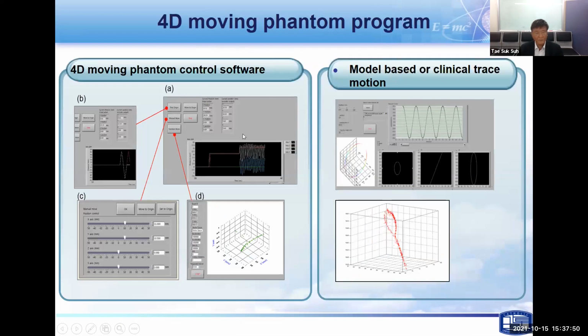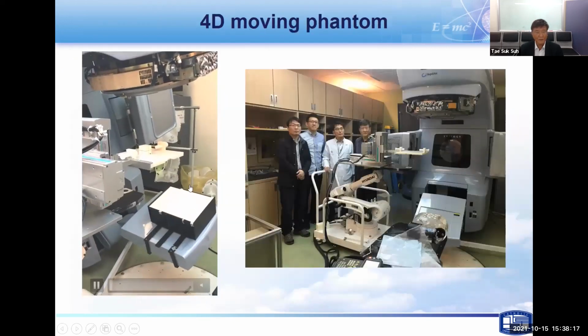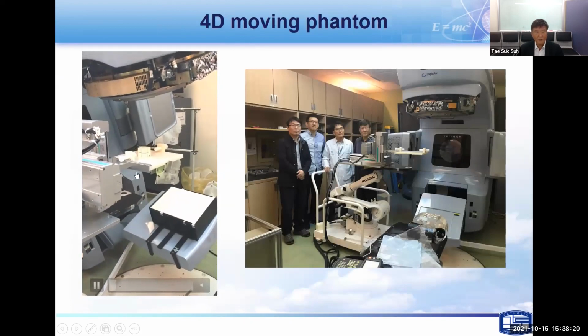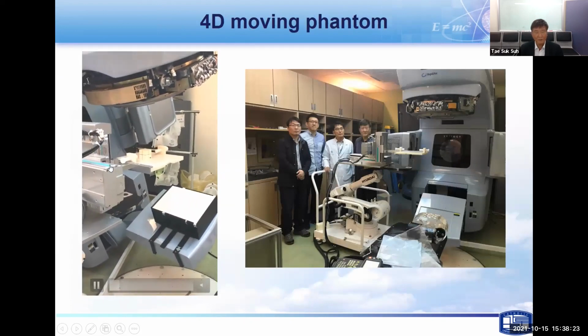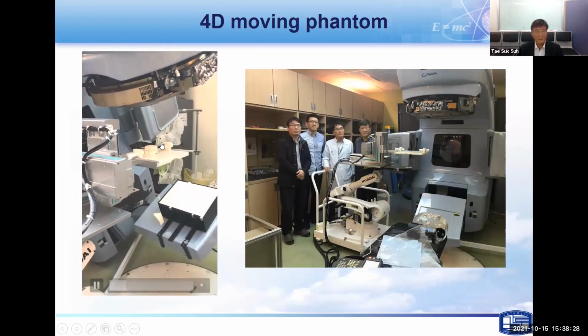To control the 4D phantom in the PC environment, a dedicated motion control software was implemented, and a model-based or clinical 3D body motion can be recreated using the developed software. So we tested a 4D moving phantom in linac room, assuming a real patient treatment. The result was good.